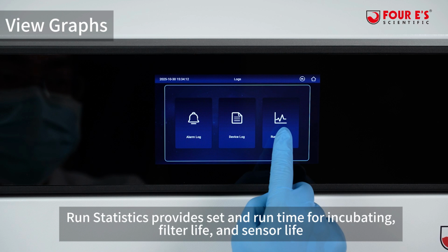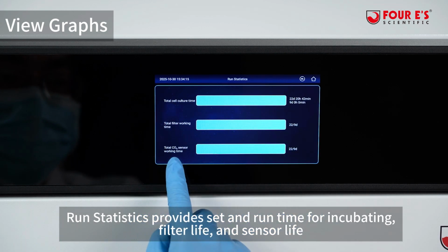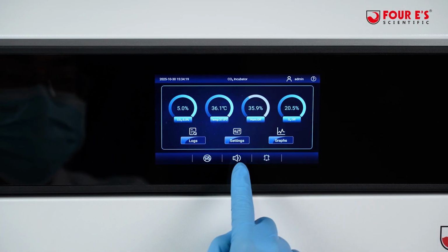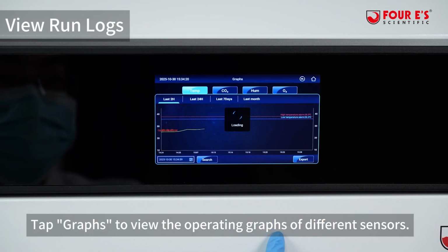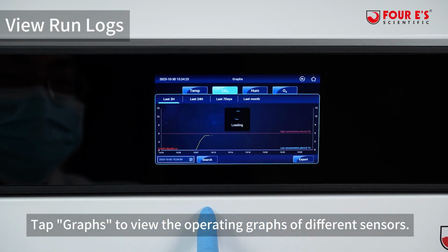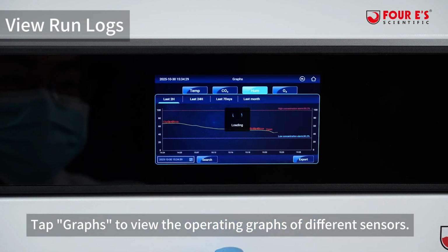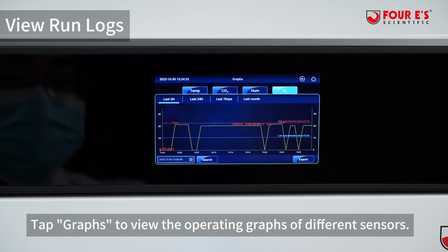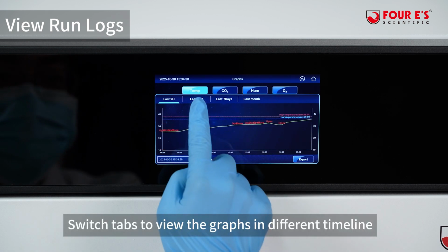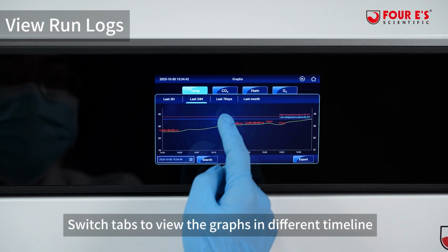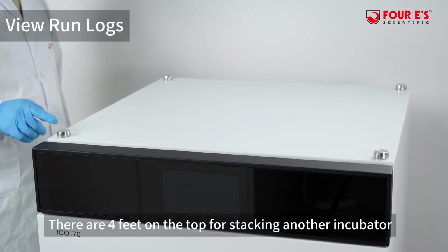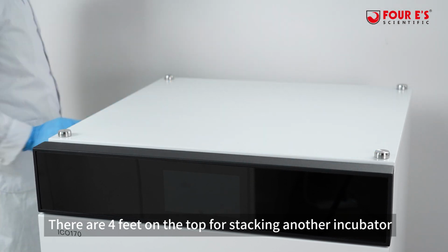Run statistics provides set and run time for incubating, filter life, and sensor life. Tap graphs to view the temperature, CO2, humidity or O2 sensor operating graphs. Switch tabs to view the graphs in the last 2 hours, 24 hours, last 7 days or last month. There are 4 feet on the top for stacking another incubator.